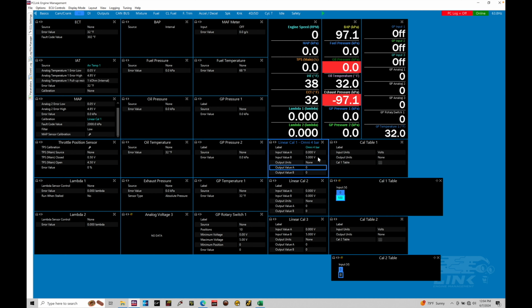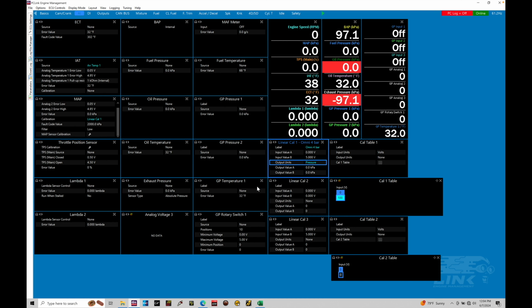And then we have our input B. This would be the maximum volt output from the sensor, and then the actual maximum pressure reading from the map pressure sensor. Now the output units are important here. We want this to be set to pressure because we're dealing with a map pressure sensor, so we're going to go ahead and select that and click OK.